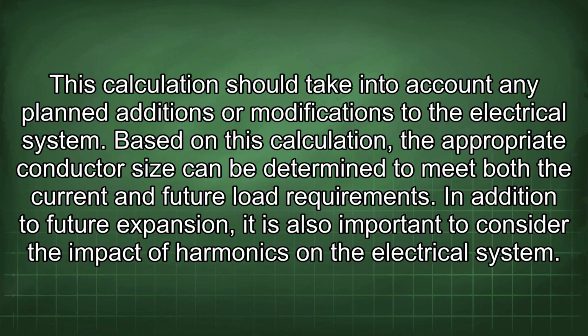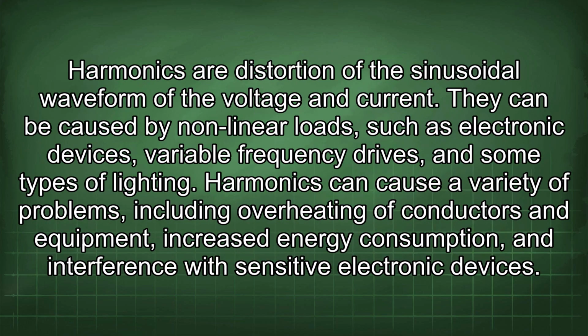In addition to future expansion, it is also important to consider the impact of harmonics on the electrical system. Harmonics are distortion of the sinusoidal waveform of the voltage and current. They can be caused by nonlinear loads such as electronic devices, variable frequency drives, and some types of lighting. Harmonics can cause a variety of problems, including overheating of conductors and equipment, increased energy consumption, and interference with sensitive electronic devices.